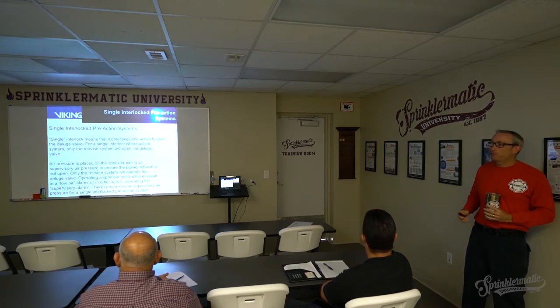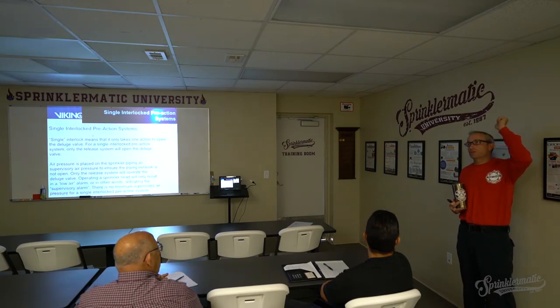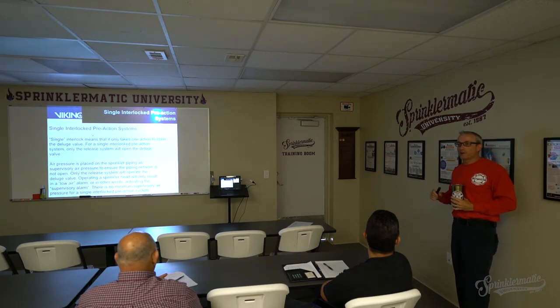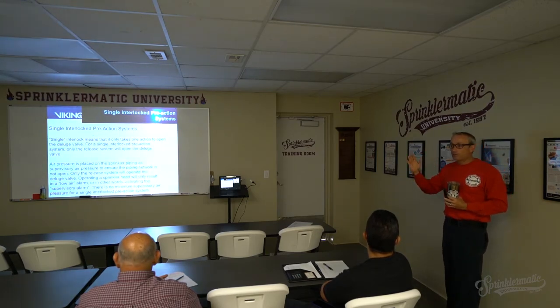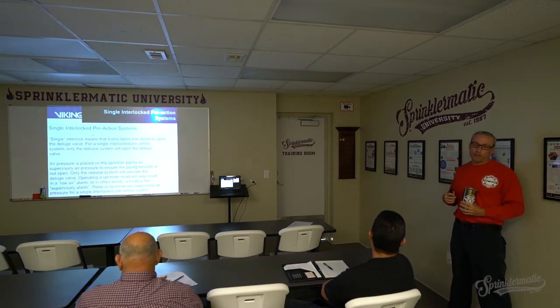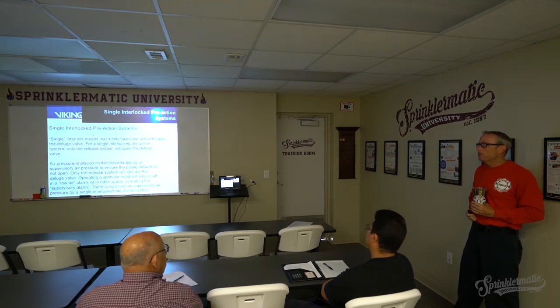So that's why a lot of times you'll see that installed. If you break a sprinkler head or somebody puts a hanger, whatever it is, an accidental break in a sprinkler head is going to discharge air pressure, but it's only supervisory air. You're going to get a supervisory low air alarm at the panel, and all you have to do is replace the head, restore air pressure, and reset the system, and you're good to go. So you don't have water flowing. The detector acts as that light switch to trip the system and allow water to flow through the valve.